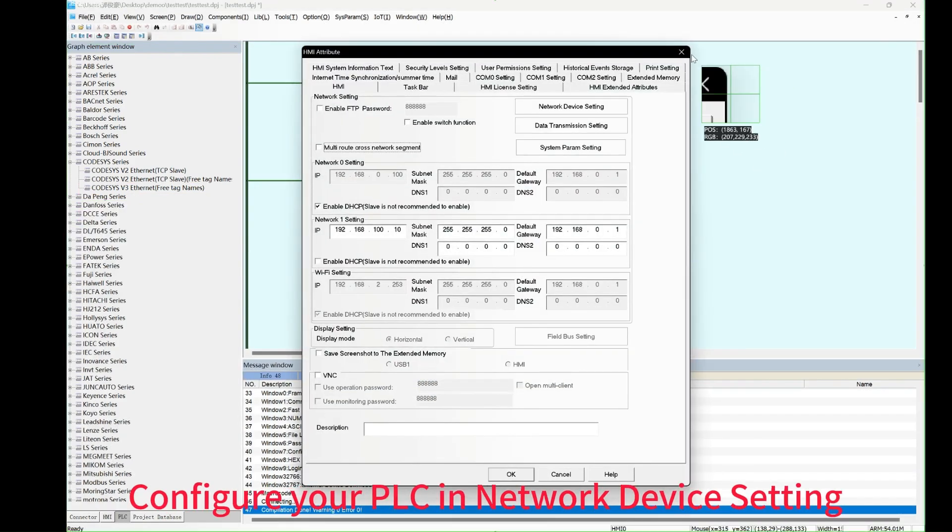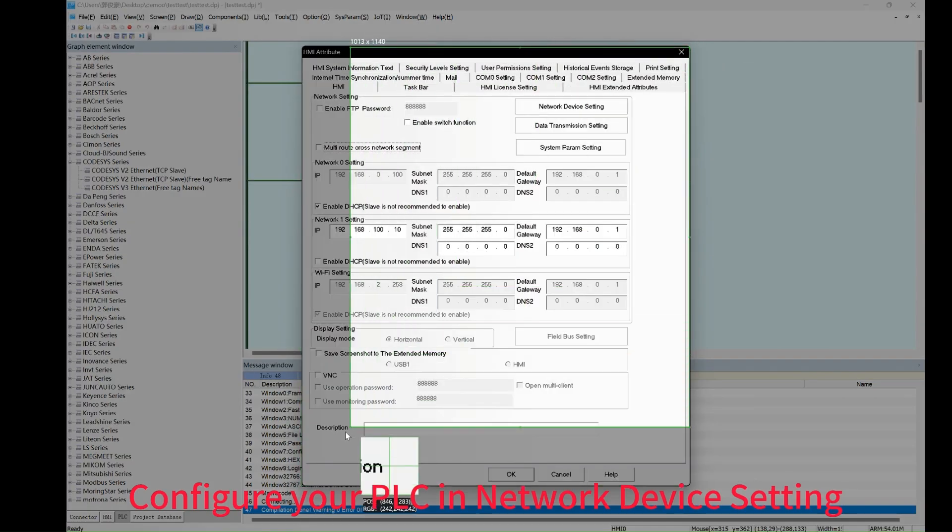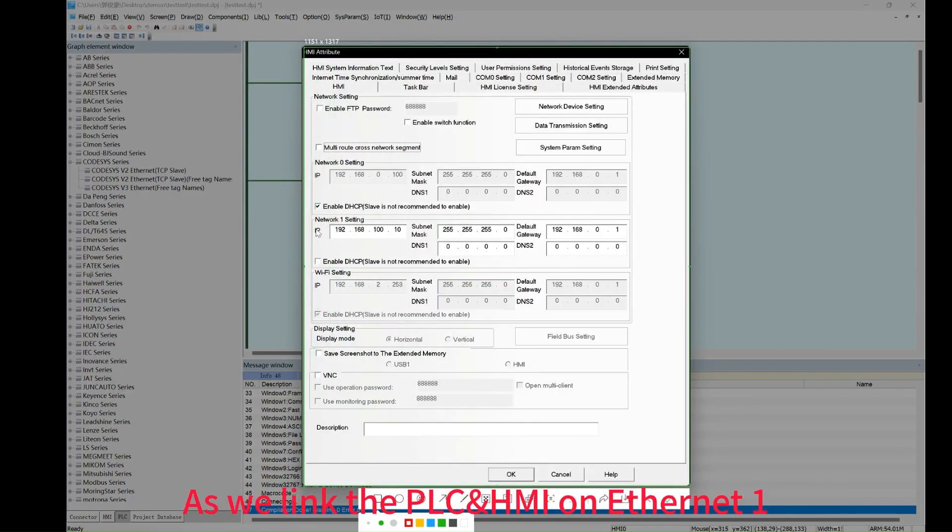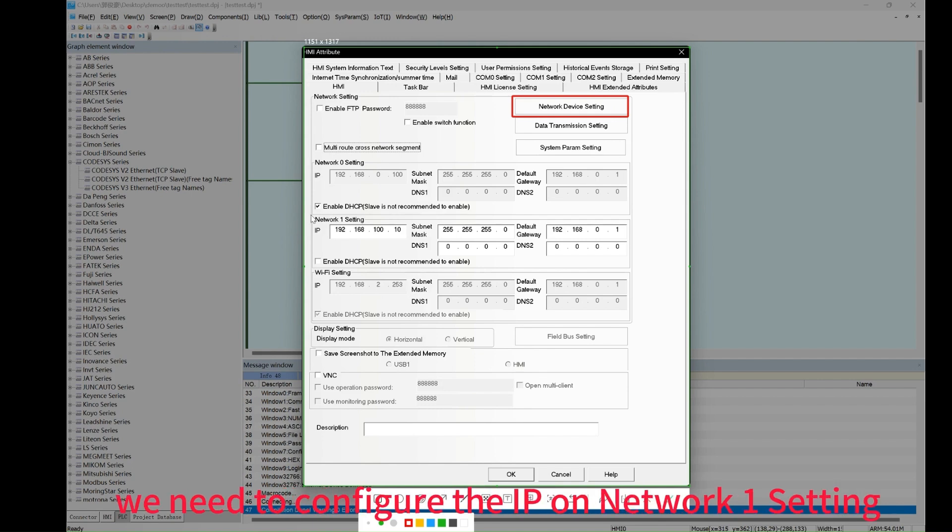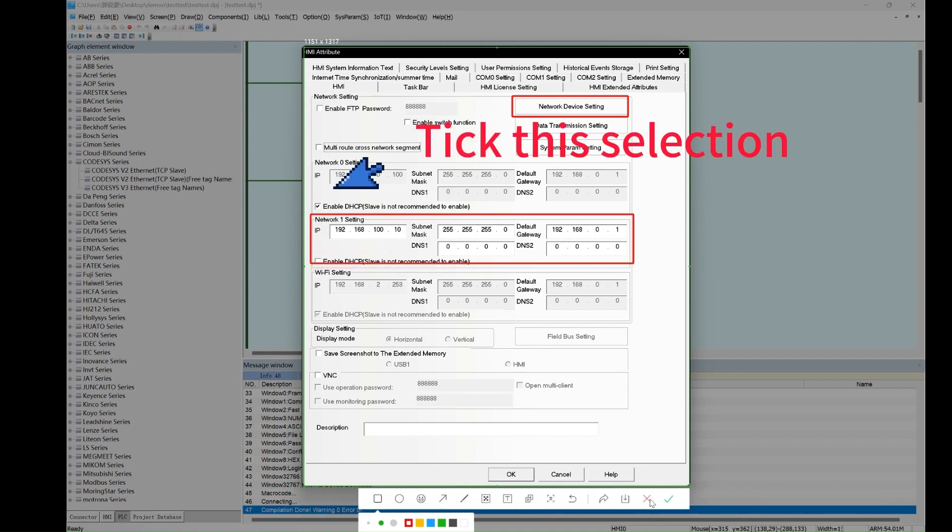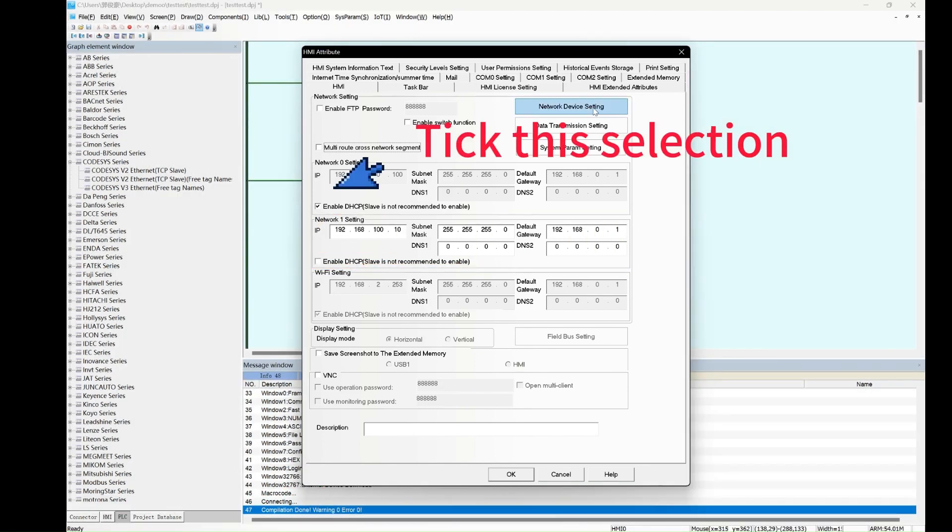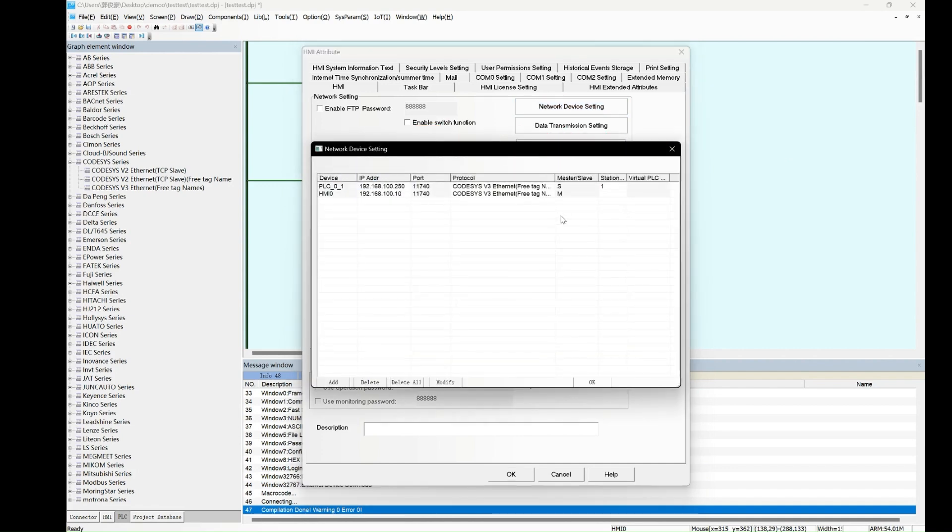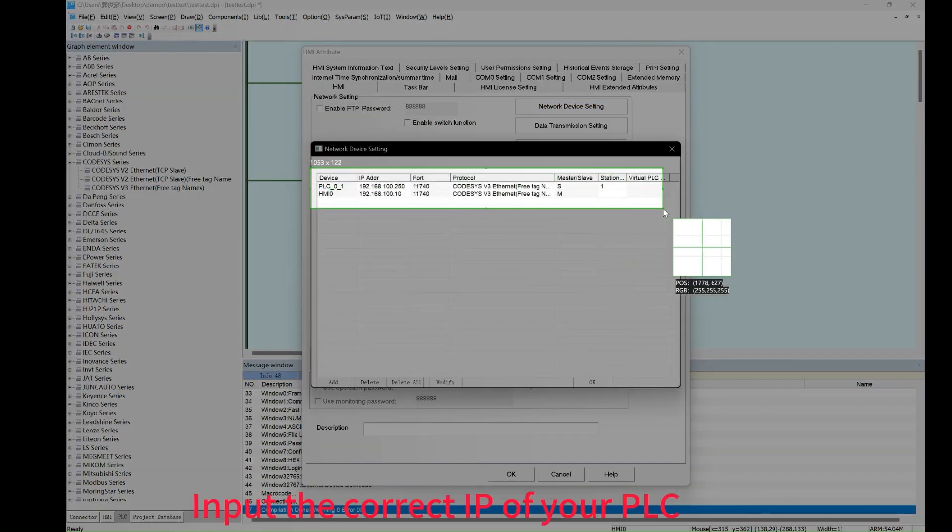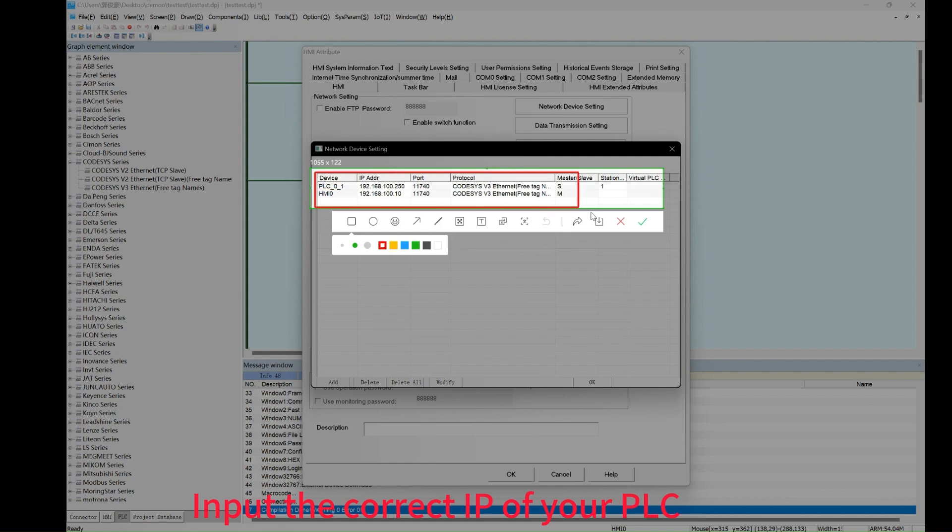Configure the PLC in the network device setting as we link the PLC HMI on Ethernet 1. Then configure the IP on the network 1 setting and select Enable DHCP. Input the correct IP of your PLC here.